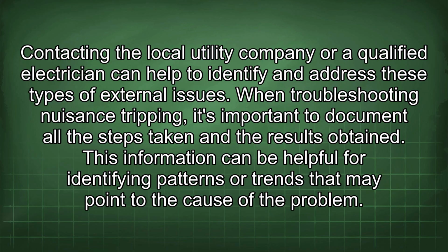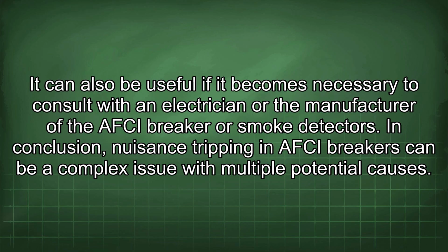When troubleshooting nuisance tripping, it's important to document all the steps taken and the results obtained. This information can be helpful for identifying patterns or trends that may point to the cause of the problem. It can also be useful if it becomes necessary to consult with an electrician or the manufacturer of the AFCI breaker or smoke detectors. In conclusion, nuisance tripping in AFCI breakers can be a complex issue with multiple potential causes.